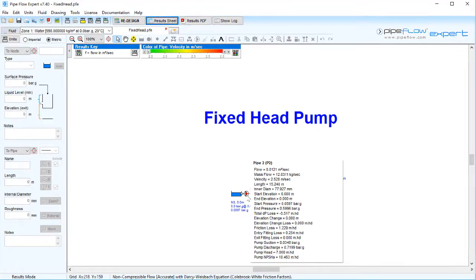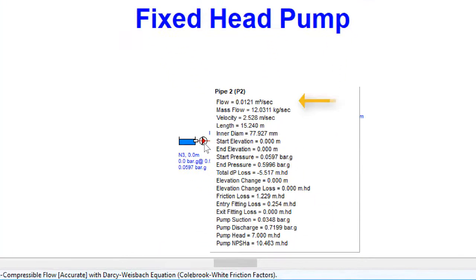Hovering over the pump, we can now see the flow rate for a specific head increase has been calculated. Adding seven meters head with this pump yields a flow rate of 0.0121 meters cubed per second.